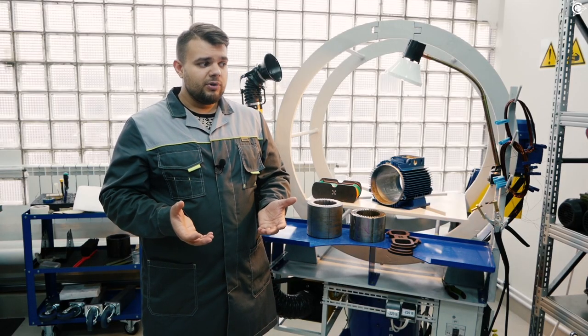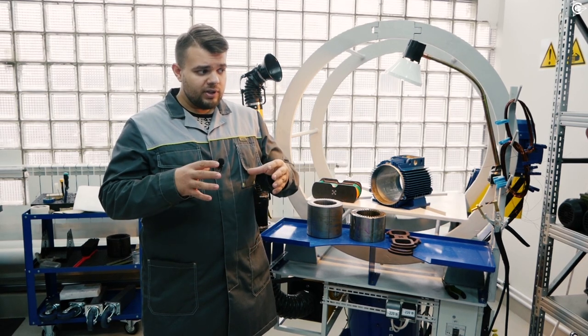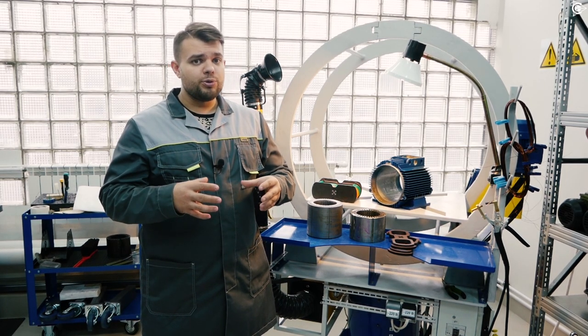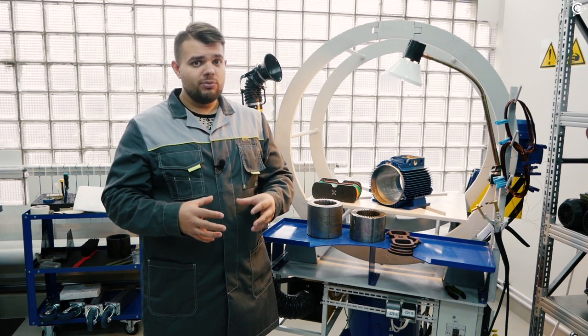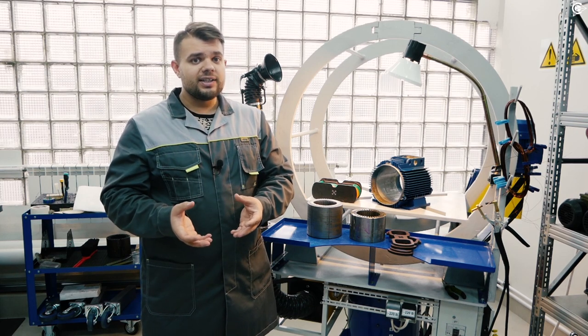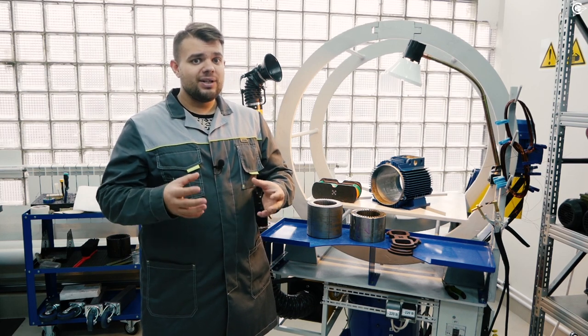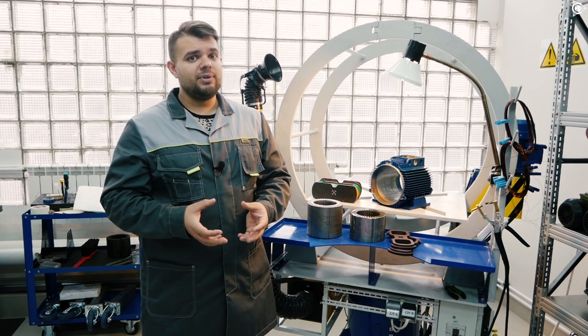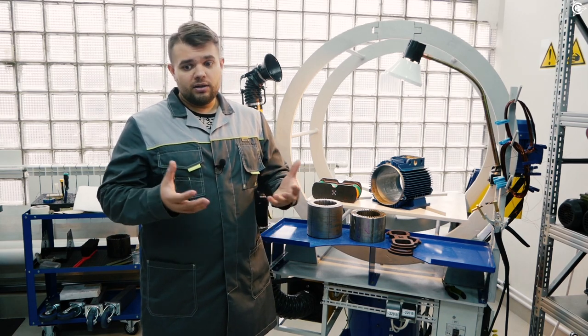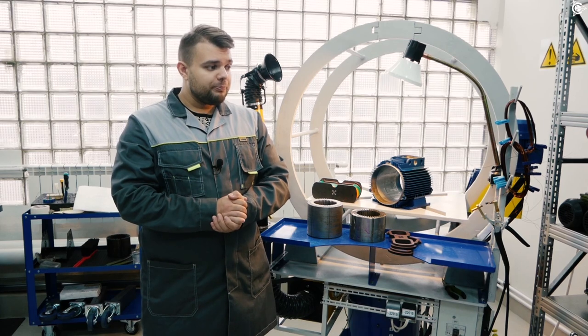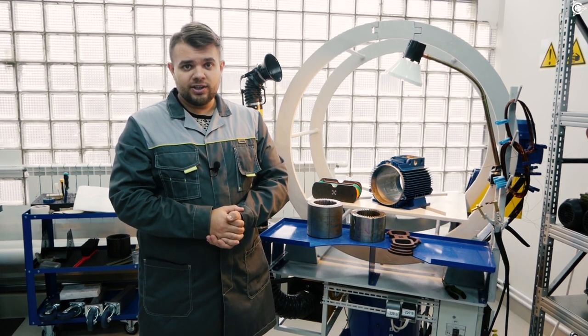As an example, I can say that thanks to using the Slavyanka technology, we can get an IE3 class motor in the frame of an IE1 motor with the same basic mounting dimensions. This is breaking news, but what else impacts the performance of the future motor?